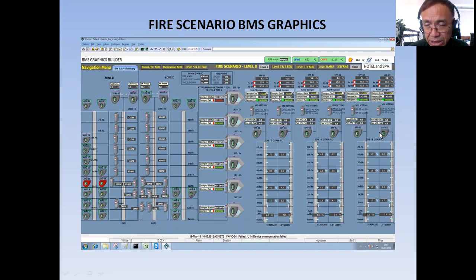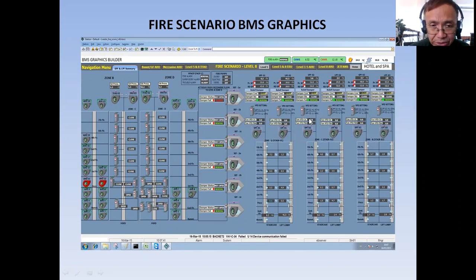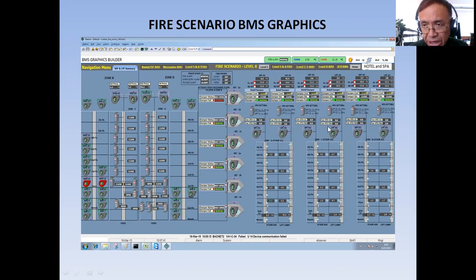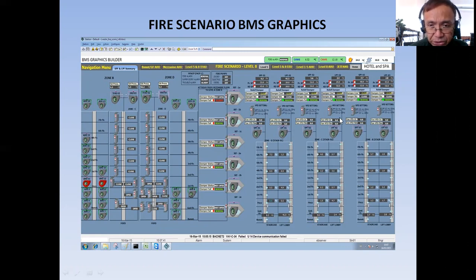The pressure is being maintained by BMS by controlling the variable frequency drive that drives these fans. The fire FDAS will be the one to run all this equipment, but the pressure in the staircase and lift lobby will be maintained by the Building Management System. The scope of maintaining the decided pressure inside the staircase and lift lobby is the scope of BMS. I'm also showing the lift damper status — if it is commanded to open or commanded to close.